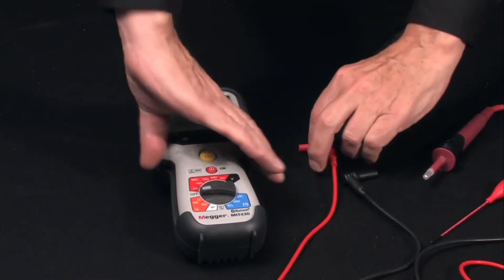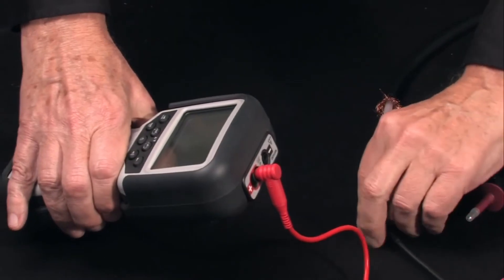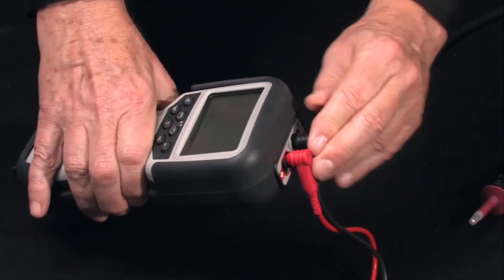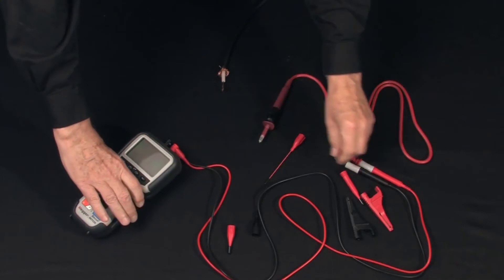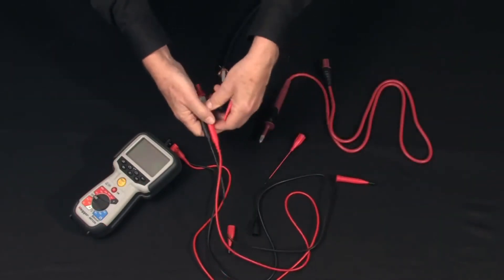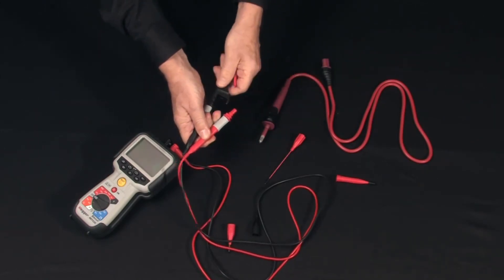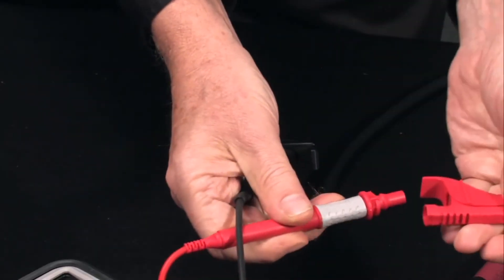Remember, an insulation test is always performed on a de-energized circuit. We install the leads in the color-coded terminals, positive and negative. For this test, we'll use alligator clips — easy-snap-on — black to black and red to red.